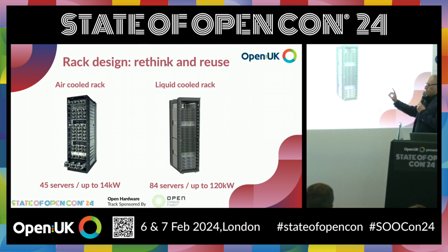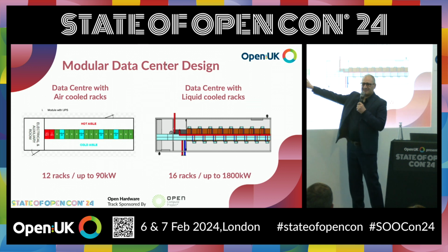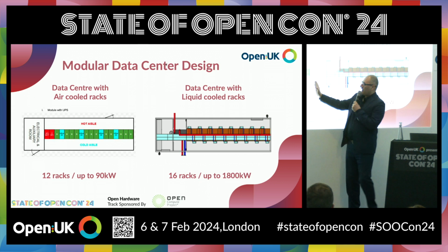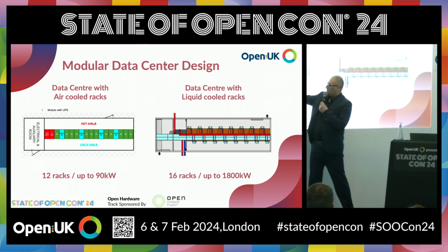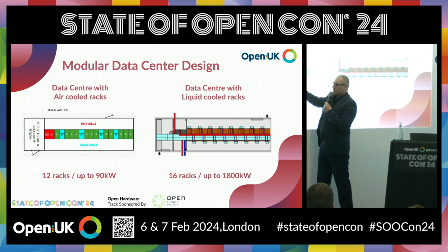When you go to this modular data center design, you will see that it's the same form factor container. Here you have 12 racks, UPSs, and 4 in-row coolers. Each in-row cooler is 30 kilowatt, 3 working. So this is where we have this bottleneck, 90 kilowatt.